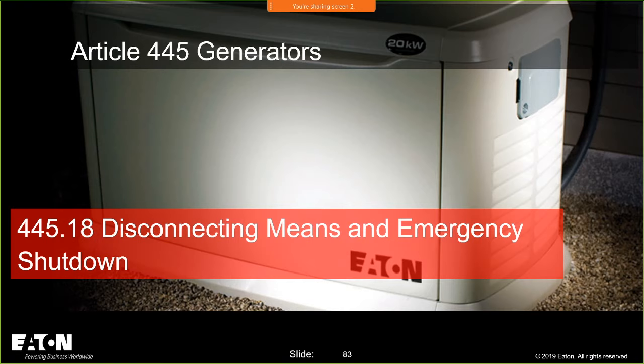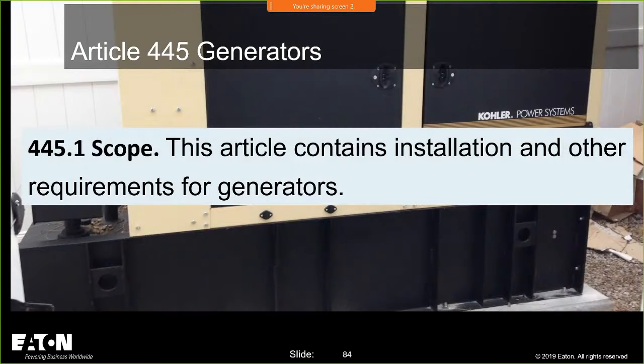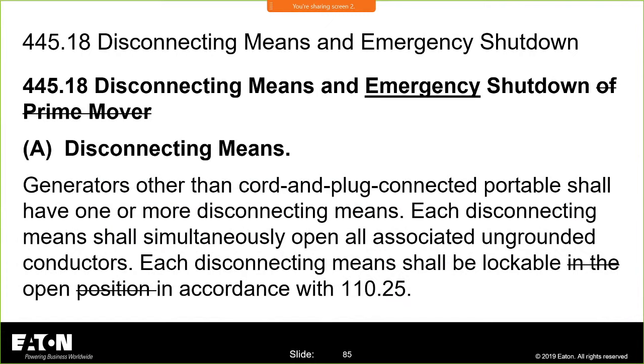445, disconnecting means an emergency shutdown. The changes you see in 445, which again is generator applications and installations, line up with the changes that we saw in 230 regarding what I called the firefighter disconnect. They're calling it the emergency disconnect, an emergency shutdown. This is for your first responders. So they aligned the requirements in 445 to shut down this generator. If you have an external generator on site, you have to make sure that you can disconnect the service, but we all know what happens when you disconnect the service. The generator is going to start, and you need to shut down that prime mover.